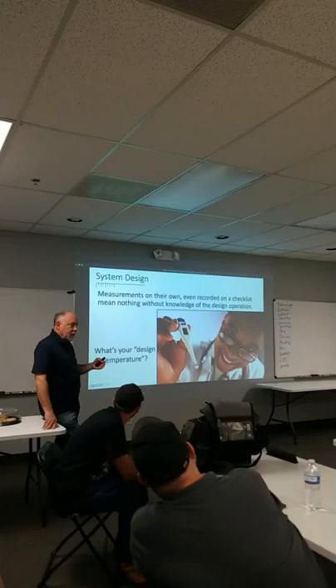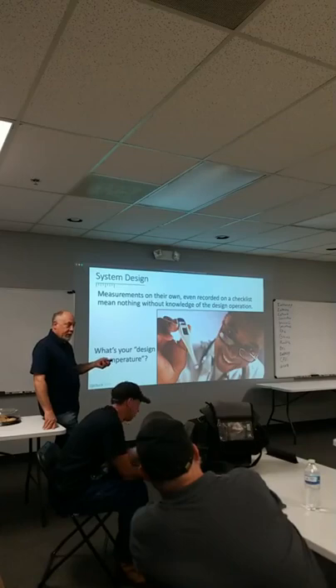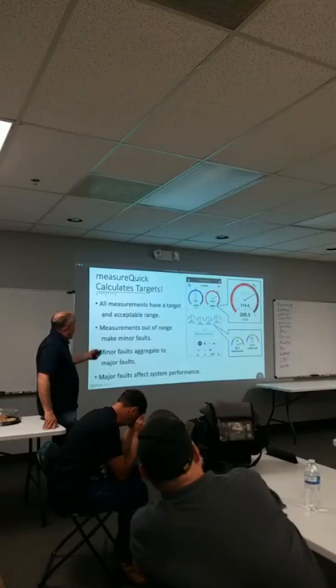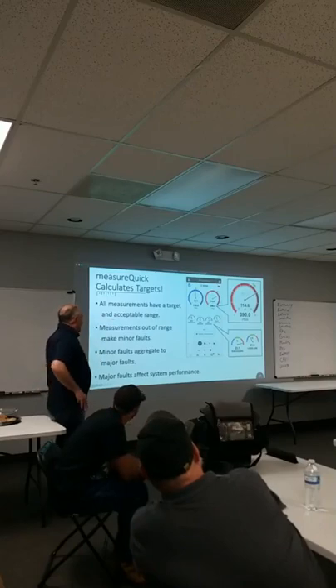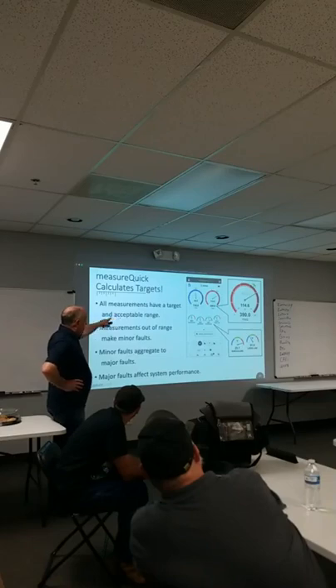If you don't know what it should be, there's no screw that you're gonna adjust to say, oh, the suction pressure's low, let me just turn it up a little bit, right? And this is a big problem we run across in the industry. So with Measurequick, what we've done is we've designed it so we can calculate all these targets, and every measurement we make has an acceptable range. And then when things are out of range, we generate what are called minor and major faults.